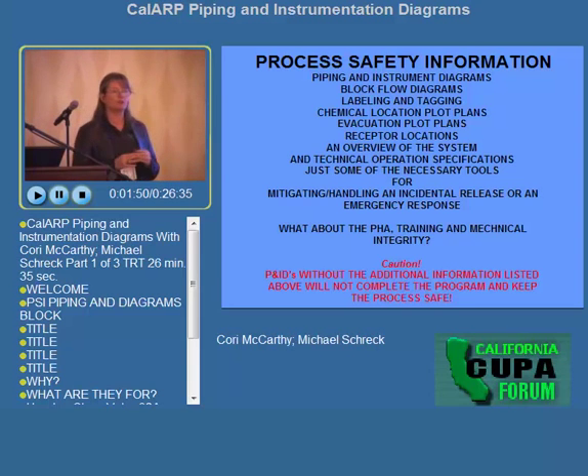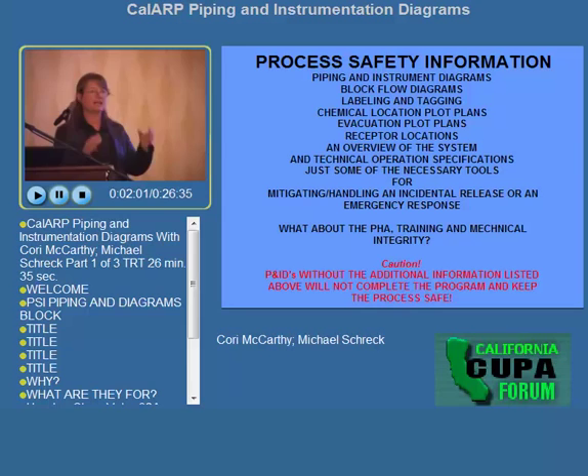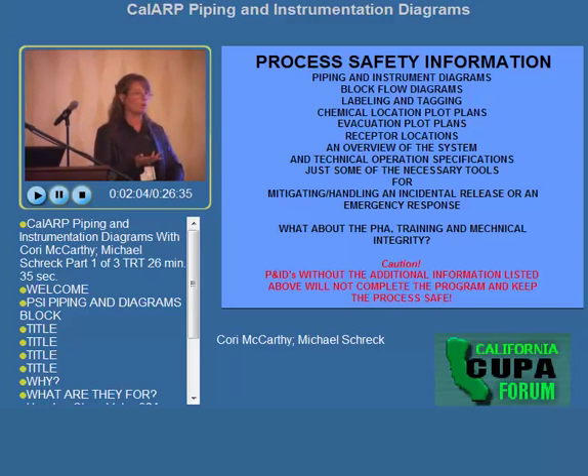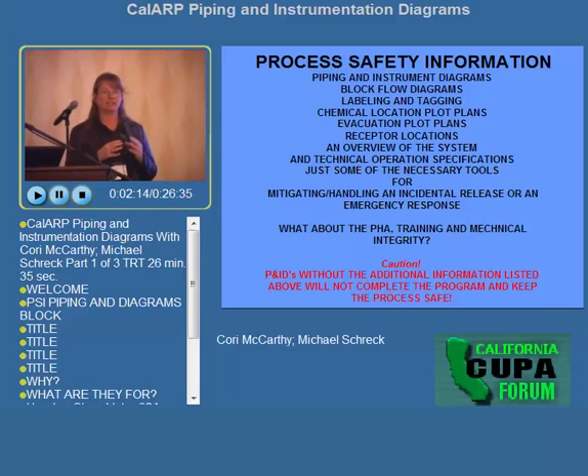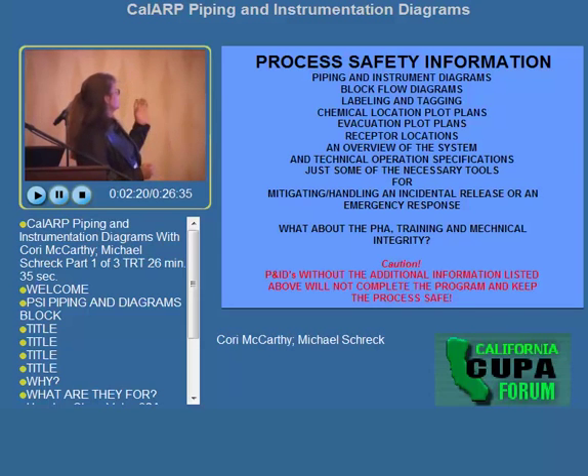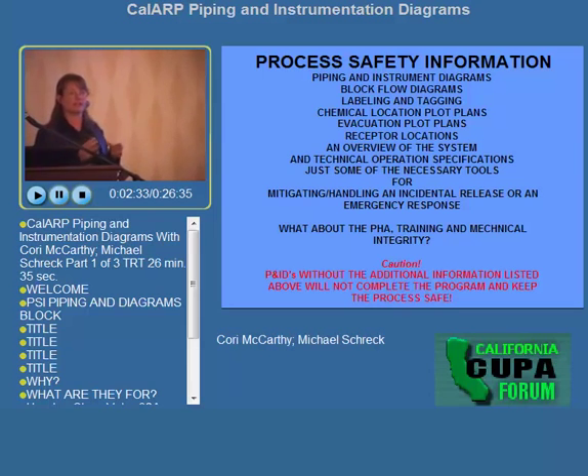We also need to have an overview of the system along with the technical operating specifications. The overview is simply stating we're taking ammonia at this pressure and temperature and using it to perform this function — whether it be cold storage, chilling water, or freezing ice cream. The more detailed technical operating specification gets very specific as to temperature and pressure within the system at the various locations. These are the necessary tools we need to mitigate and handle incidental releases or true emergency responses.